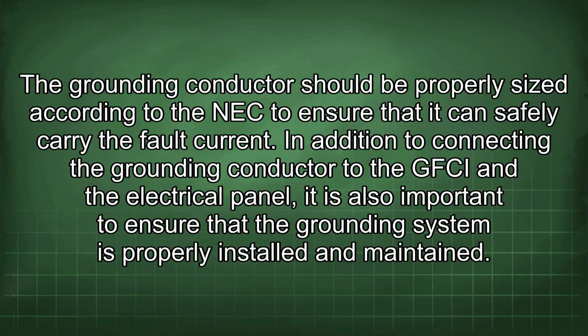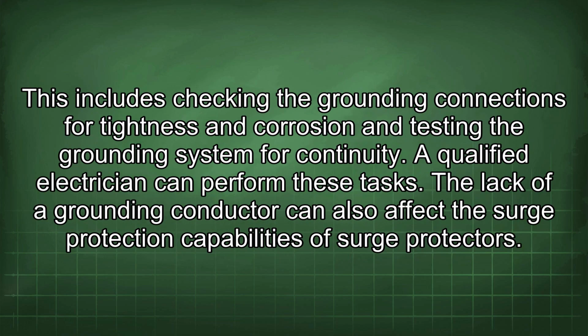The grounding conductor should be properly sized according to the NEC to ensure that it can safely carry the fault current. In addition to connecting the grounding conductor to the GFCI and the electrical panel, it is also important to ensure that the grounding system is properly installed and maintained. This includes checking the grounding connections for tightness and corrosion and testing the grounding system for continuity. A qualified electrician can perform these tasks.